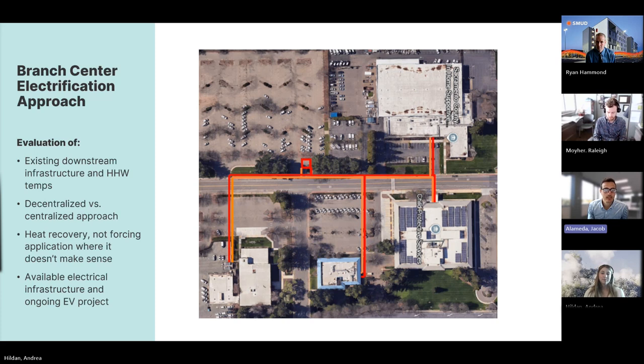To do that, each building was given its own hydronic loop with a small air-to-water heat pump. Some of the bigger buildings were recommended a heating electric boiler to supplement that, like I talked about before, where 20% of the capacity is electric boilers. It was tough because these are existing buildings and you're trying to add a large air-to-water heat pump at them, so we worked closely with Raleigh to see what locations they were comfortable putting a new air-to-water heat pump at, trying to mitigate structural improvements and sound nuisance.